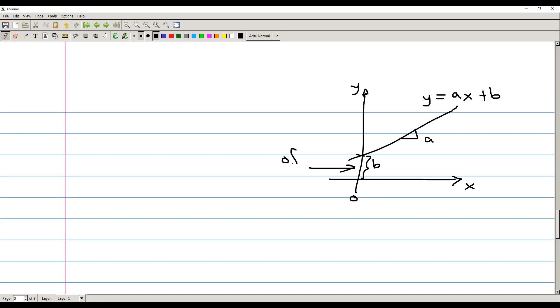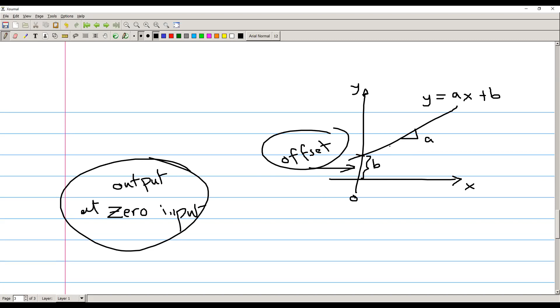This offset means that when you have a 0 input, this is the output at 0 input. This is called the offset. This is very important, because otherwise you won't know this curve. In order to have the complete relationship between the output and input of a sensor, you have to know the offset and the slope. The slope is the sensitivity, and the intercept is the offset. You need to know both of them.